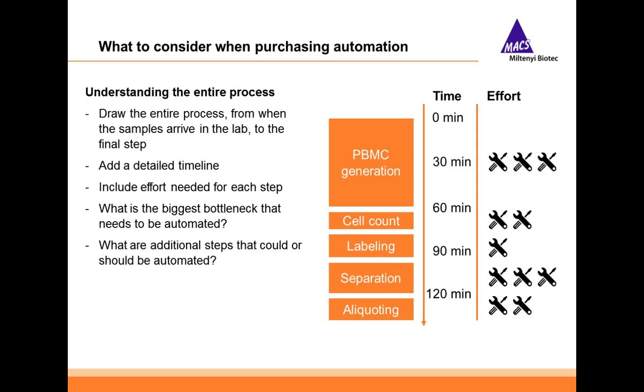When I talk to customers about automation, I ask them to draw the entire process from when the samples arrive in the lab to the final step. This is a generalized and simplified process that might go from PBMC generation to cell counting, to cell labeling, then separation, and an aliquoting step at the end. Normally I'd go on a big whiteboard and add all the details — such as number of samples, type of samples, and volume — but we'll use this as a simplified example today. Once you have your process overview, add a detailed timeline. If you're not sure about the times, start a stopwatch and take notes next time you do this.